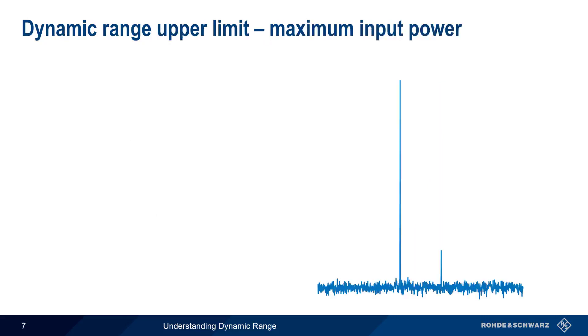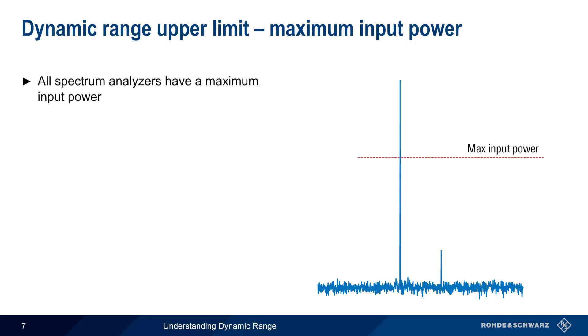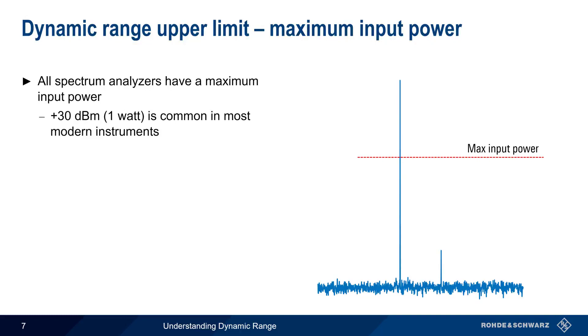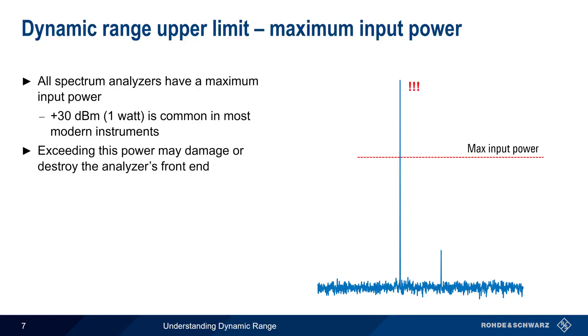Next, let's look at what limits the upper end of dynamic range. All spectrum analyzers have a specified maximum input power. In most modern analyzers, this is +30 dBm, or 1 watt. This maximum safe input power is usually printed directly next to the input connector itself. If maximum input power is exceeded, the analyzer's front end can be permanently damaged or destroyed, so clearly this maximum input power represents the maximum upper limit of dynamic range.